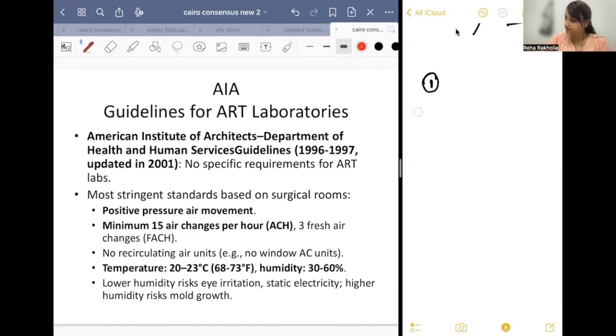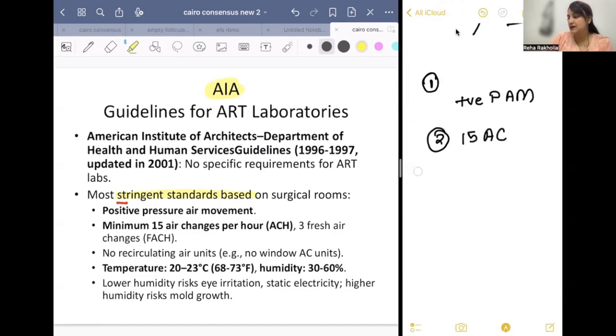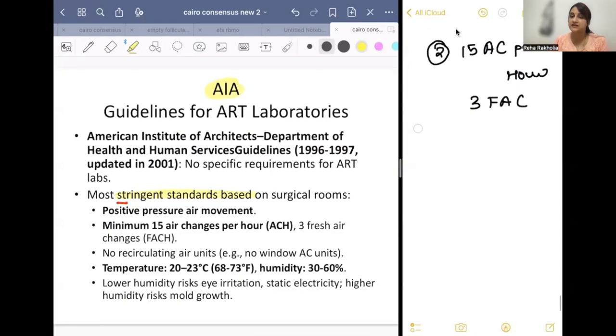The most stringent standards, based on surgical rooms, were followed according to AIA. This included positive pressure air movement, 15 air changes per hour with 3 fresh air changes, and no recirculation, with no window ACs allowed.